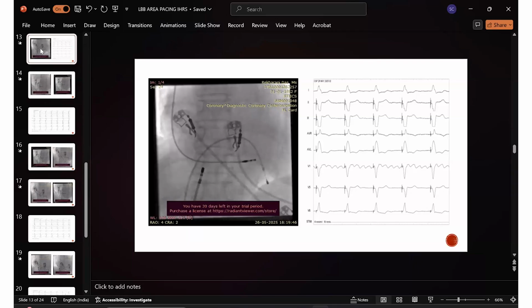So it's always good to inspect the lead body as such. If you keep using it repetitively during a tough procedure, with multiple attempts, look to see if there is insulation crimping, particularly with the Abbott Tendril, where the insulation crimping is sometimes permanent. You can actually feel the crimping on the lead, and you should definitely change the lead at that point. That's another thing. Thank you.